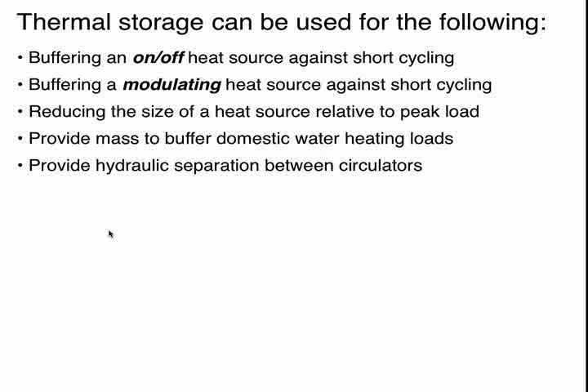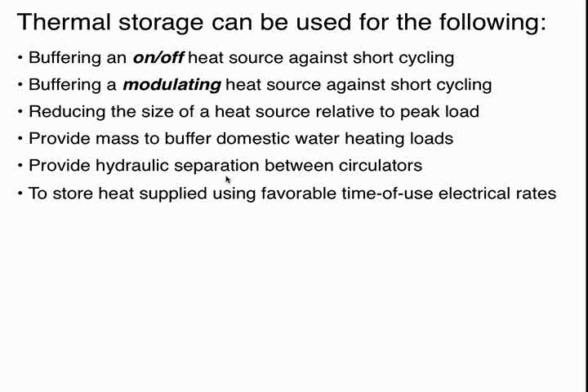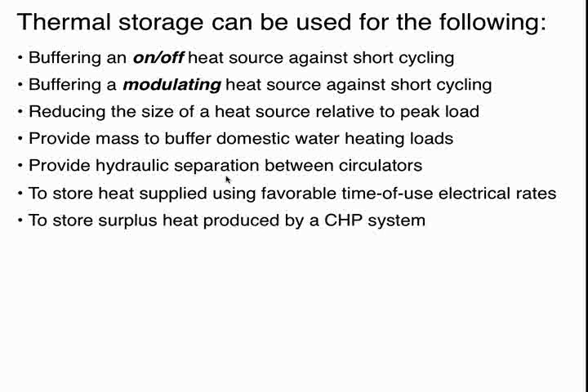Now, there are ancillary benefits to thermal storage. A properly configured thermal storage tank can also provide hydraulic separation when we have multiple circulators in a system, and we don't want those circulators to interfere with each other. We'll show you some schematics on at least 2 different ways you can set up a thermal storage tank so that it also serves as a hydraulic separator. We can take advantage of favorable time of use electrical rates. Some of you may live in utility areas that have off-peak electric available at night for perhaps half the cost or even a third of the cost of what the electrical rates are during the day. Again, we can run those heating elements when the electricity is cheap. In a sense, we're buying electricity when it's on sale from the utility, storing it in the thermal storage tank.